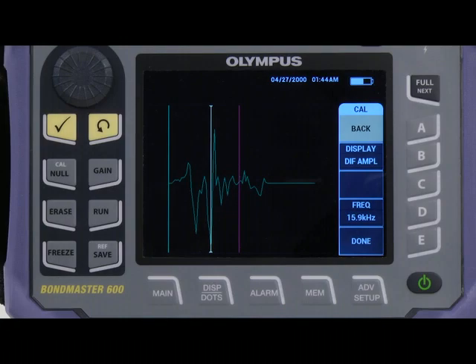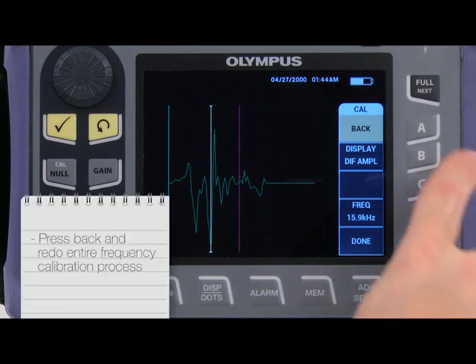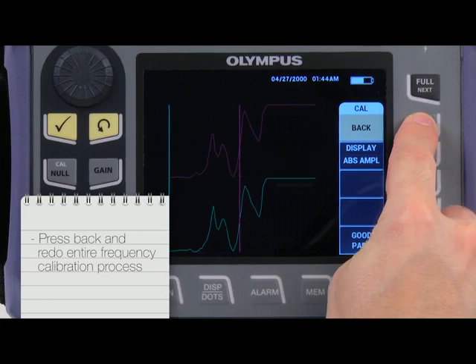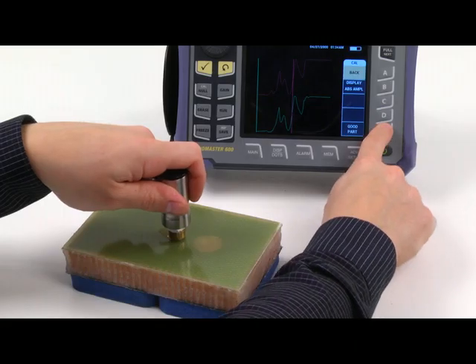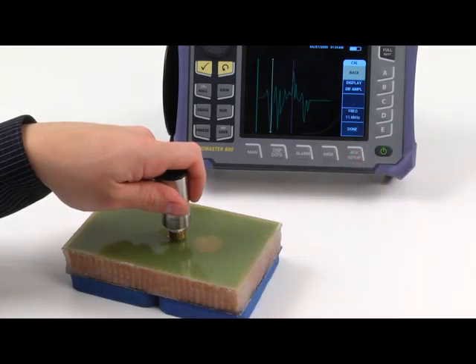However, if you obtain several peaks, this may be a sign of problems or a failed calibration. If you have a problem, first try pressing back and redoing the entire frequency calibration process.